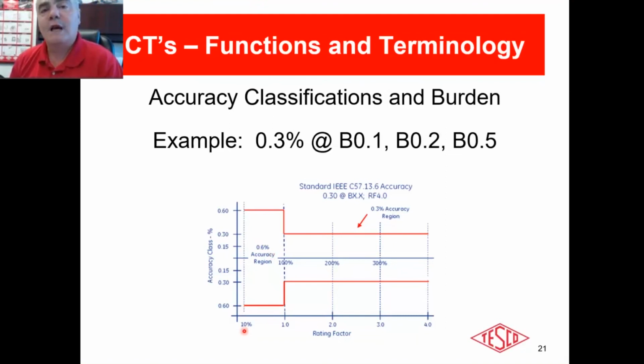If I have oversized my CTs, either by making the classic mistake that I just mentioned earlier, oh, he could go up to 800 amps, therefore we're going to put 800 to 5s. Big mistake made by people who didn't quite understand what the CT was and how you read the faceplate and what it actually means, all right? So if your boss made that mistake, try not to bring it up to him unless you can do it in a very nice way. It's not that people are stupid, it's just that people don't know. So they could have oversized the CTs right from the beginning.